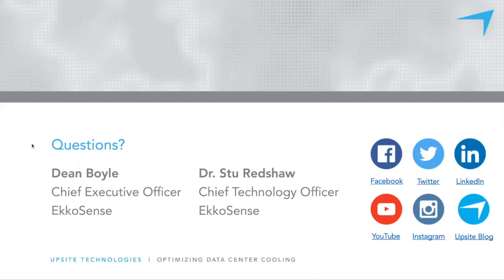Yes, we are. There are two elements to that. There's a simulated test, where a unit is stood down and removed entirely from the overall heat loads, and then you reconfigure the zones of influence to take up and pick up that heat load. But there's also supporting the teams on the ground who physically turn units off to undertake resilience testing, and providing them with the tools at the same time to monitor that activity in exactly the same way. So yeah, we'd like to think that we correctly look at those.